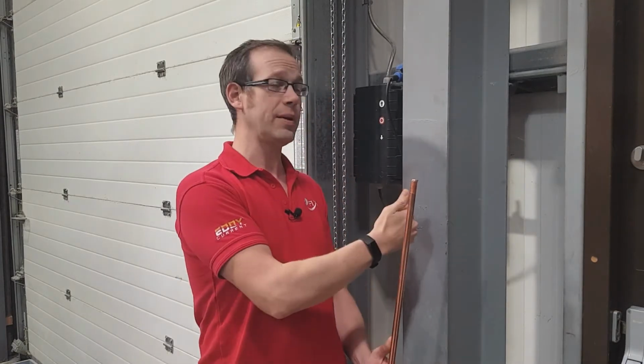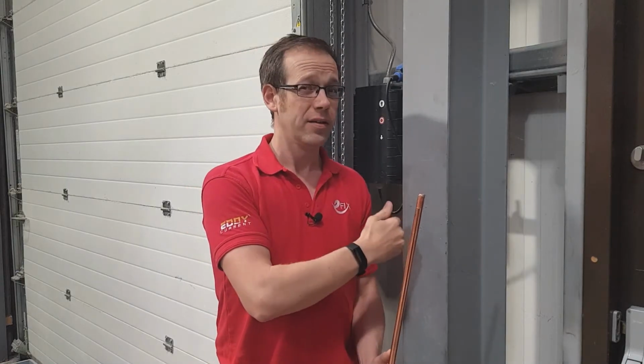So we're being very much discouraged from using an earth electrode in the way just outlined. The reason for this is that if the earth electrode for the charging point goes into the ground just next to a piece of earthed metalwork from the building, such as a gas or water pipe or structural steel, then it's possible the electrode could be so close to that bonded metalwork that in the event of losing the combined neutral and earth conductor to the property, the earth electrode could become live due to touching or even just being in the proximity of the building metalwork. So it's pretty clear that we're being discouraged from using an earth rod for this reason. However, there may be another reason to use an earth electrode, as we'll see a little bit later.